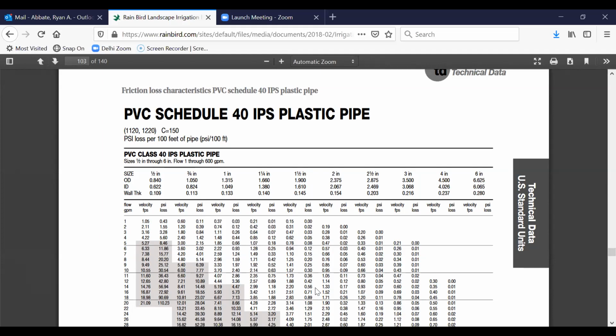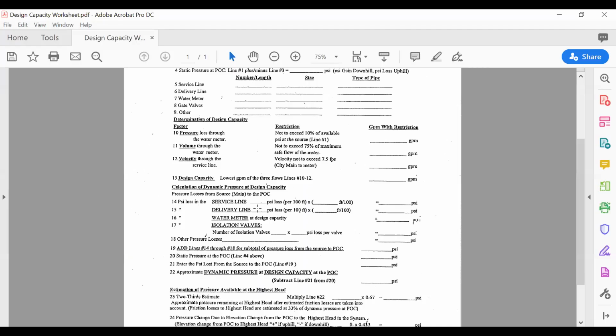We're right where that pressure section is. I'm kind of going back. So 0.89 here, because that's our PSI loss. And then our length is 50 feet, so it'd be 0.50. So 0.89 times 0.50, going around, yeah, so 0.45. That should be 0.45 PSI loss.